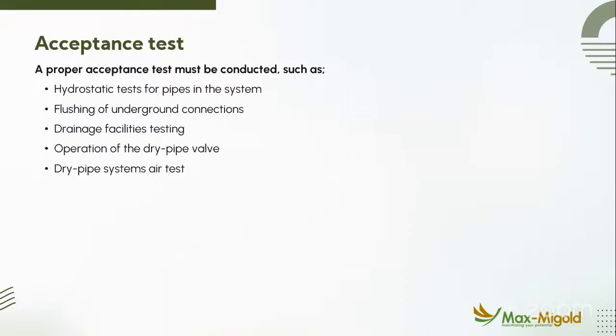There must be drainage facility for testing, which we call the inspection and testing drain points. How do I know that there's water on the line on the sprinkler system if I don't see water coming out? So they construct a drain point with water, with the pressure gauge, and of course the control valve, where we can actually open the water, and the water should come out of the drain valve. It means that the water is on the line because the drain point is actually along the line. So water should come out of the drain point, then that means there's water on the line. All right.